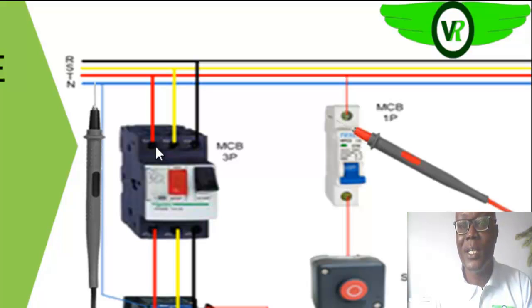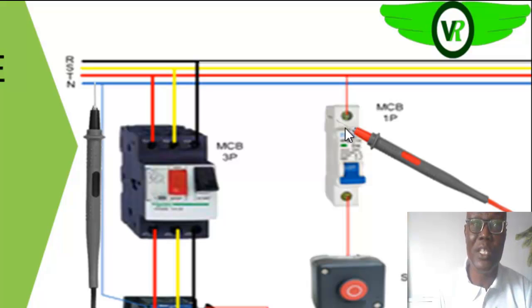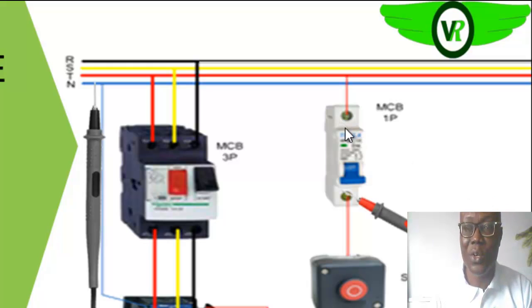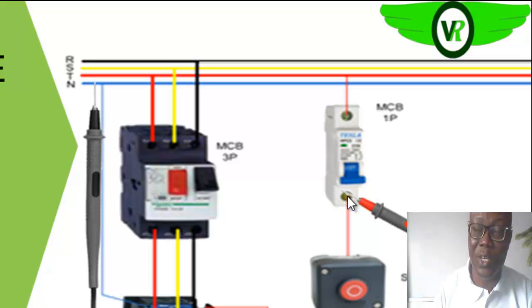Then next, we'll test the input to the circuit breaker that is feeding the control circuitry. Okay, so in these two, we are supposed to have the 220 volts. That is the low voltage that we expect to go into the control circuit. Okay, then next, when you test the output of that particular circuit breaker, while the circuit breaker is closed, you have 220. Okay, so you switch the circuit breaker on and off to be sure that the circuit breaker is working.